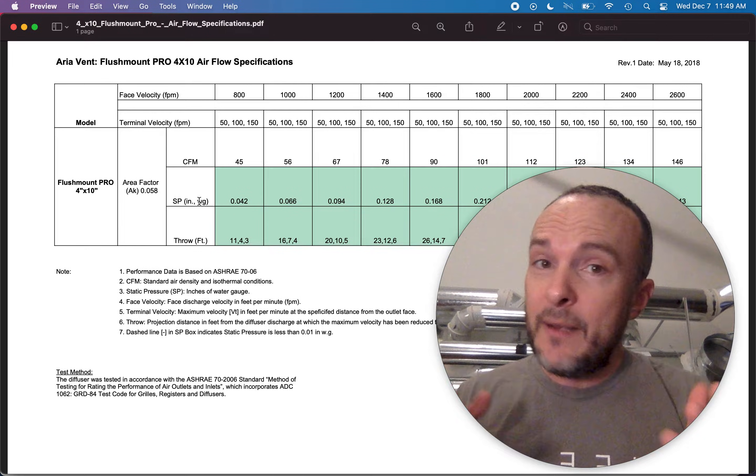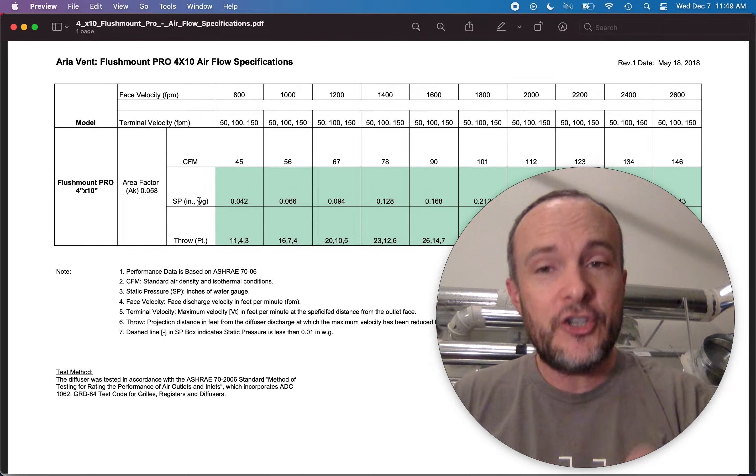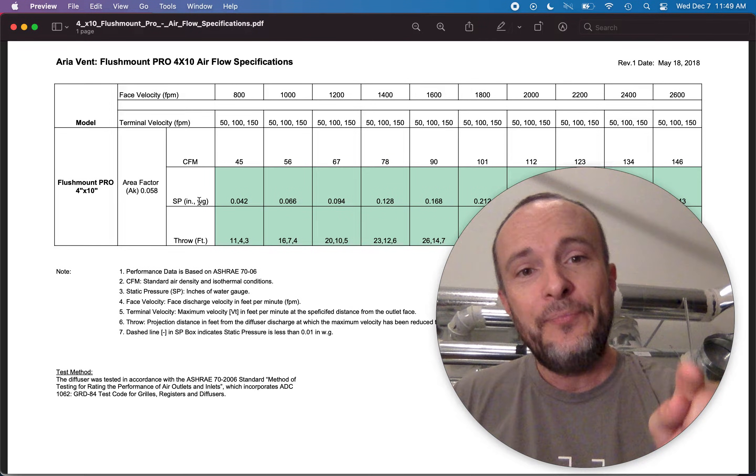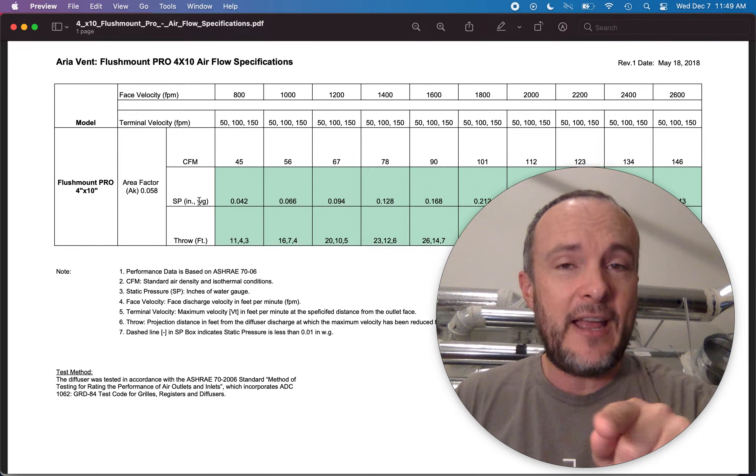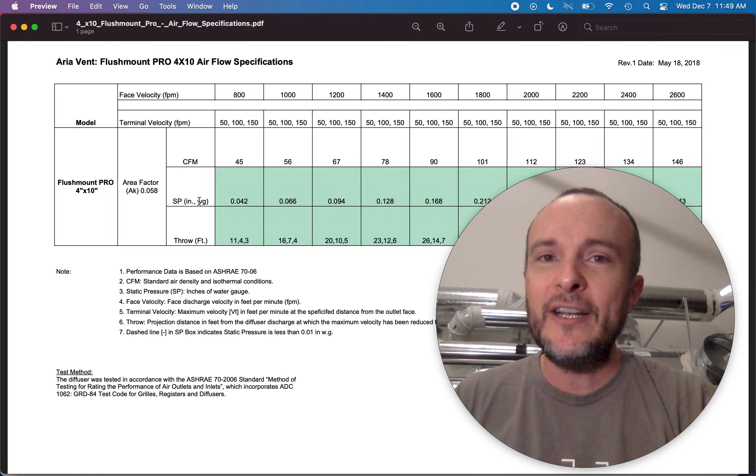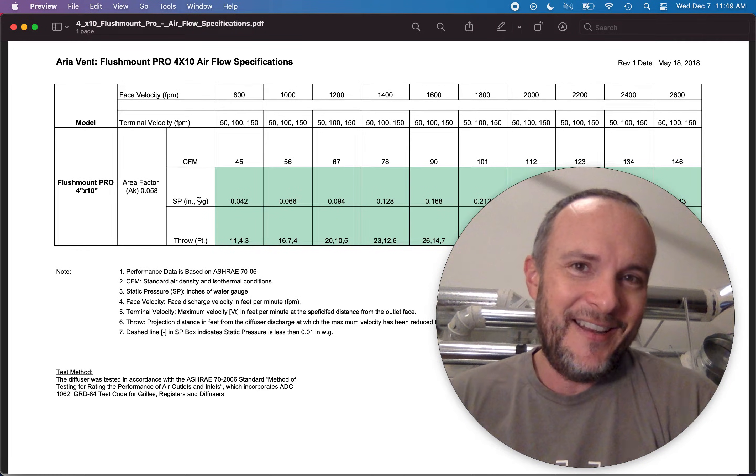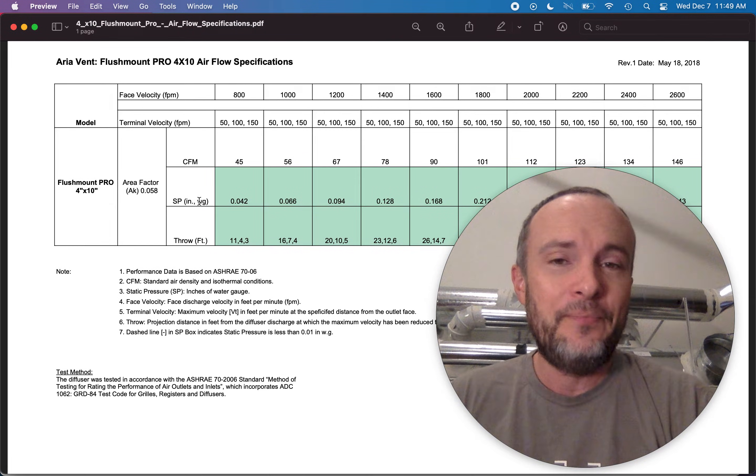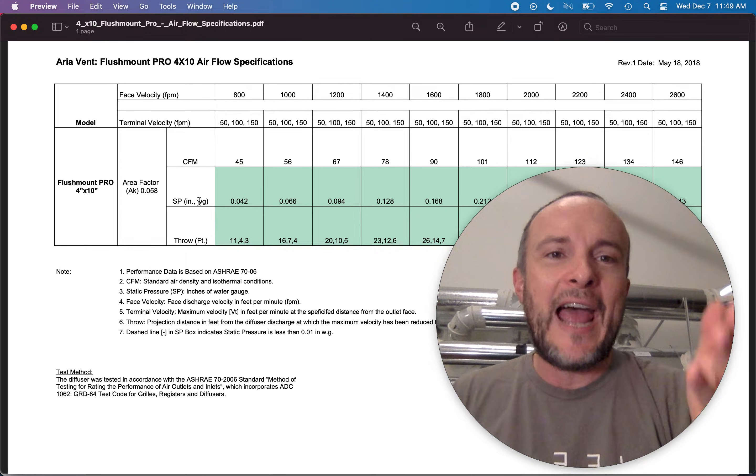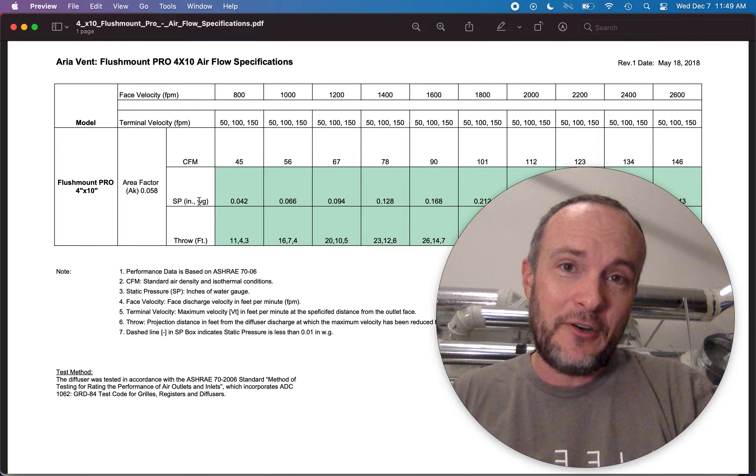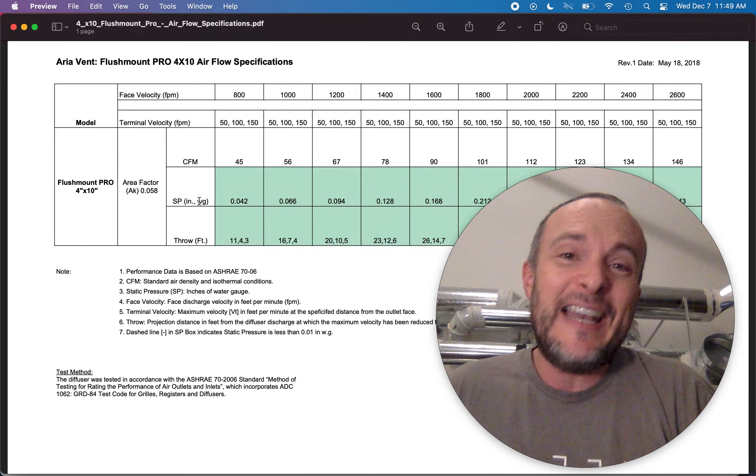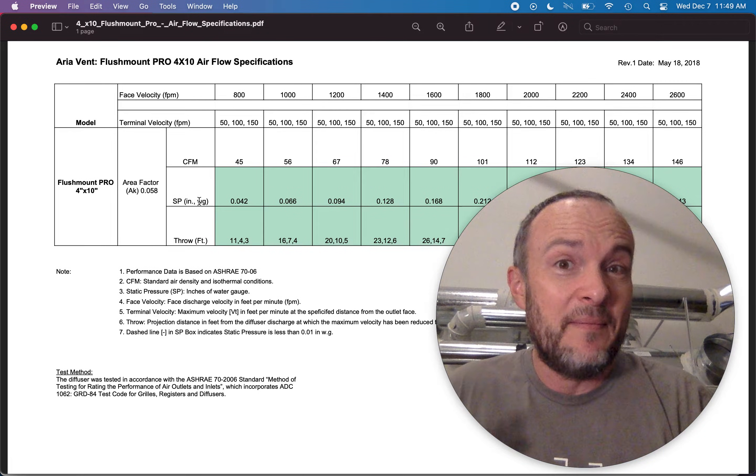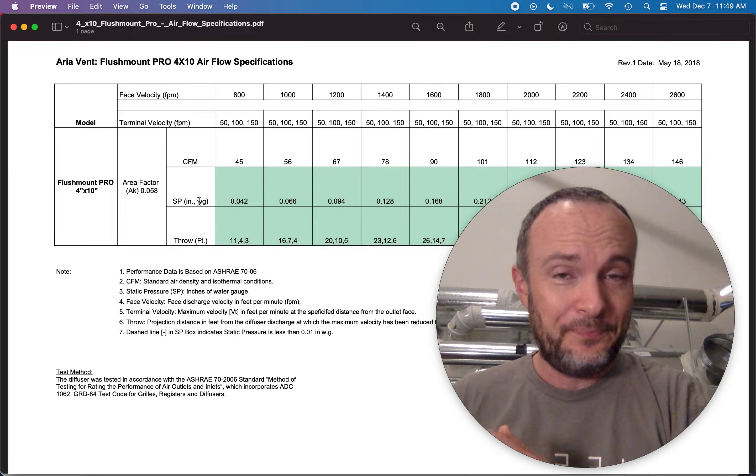Now it might be that they are doing that so that the performance in CFM of these grills doesn't look as bad as it really will in real life. Because we're not going to run these grills at 2000 feet per minute as the salesperson from ARIA told my client he might be doing. He's going to be running it at 500.